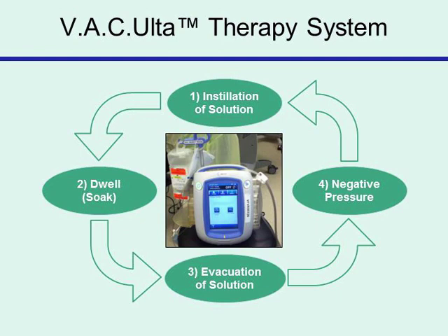The VAC Ulta therapy system has four key components: the instillation of solution; the dwell, or the time the solution is left to soak on the wound surface; the evacuation of the solution removed through the drainage tubing portal; and the application of negative pressure therapy, which takes up the majority of the cycle. For example, the negative pressure therapy will often be for several hours, while the dwell time and instillation will be just for a few minutes.